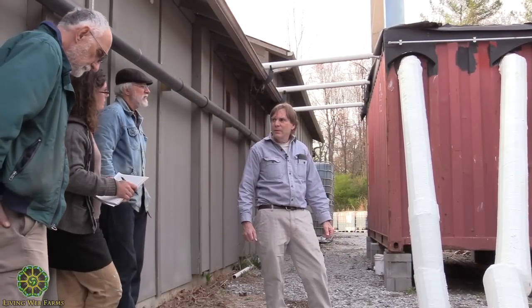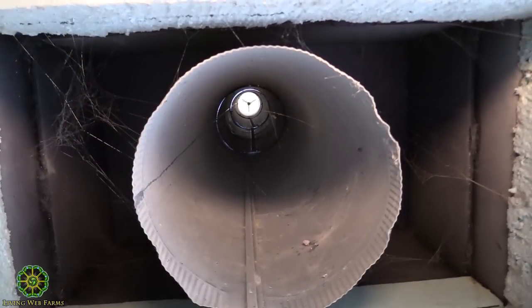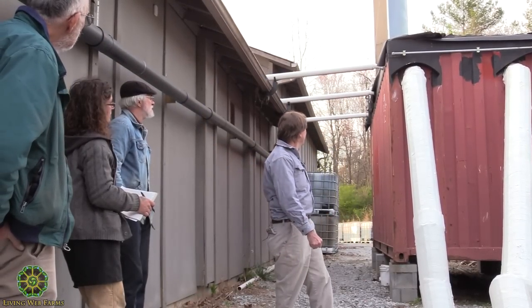How far apart are the pipes? Five feet for each course — five feet of earth between each pipe. The pipes themselves, I'd say four to twelve inches in diameter — six inches is great because it's available and fairly inexpensive. I think it's about a dollar sixty-two a foot. Would it be easier to get air to flow up the thermal chimney with a bigger or smaller pipe? If you used a bigger pipe you'd have to have a bigger chimney, and you may not want to dedicate that much.